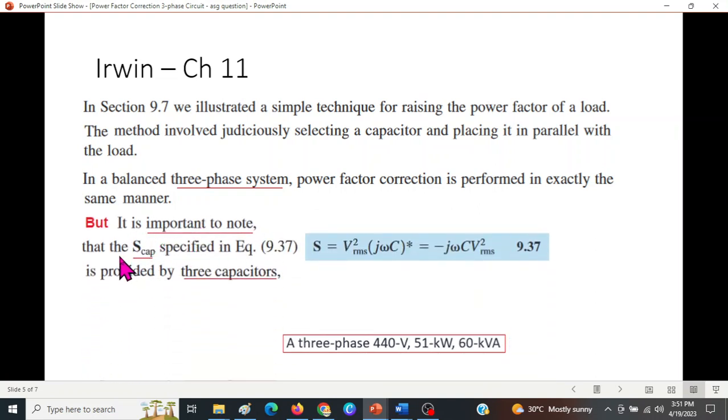It is important to note that the S capacitor or Q capacitor or Qc specified in this equation is for three capacitors. So we have to keep that in mind. For single capacitor we have to divide Qc by three. In addition, Vrms in equation is the voltage across each capacitor. Now this was the confusion in the question. It was given like this: a three-phase 440 volt. This power and the kVA rating, these are all for three phase. But what he is saying is that this voltage, 440 volt, is actually the voltage across each load, each capacitor. This is the point that we have to keep in mind.